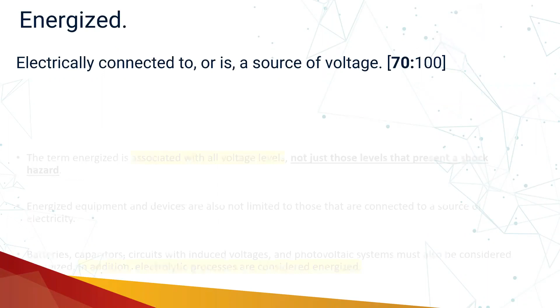We have seen that 50 volts and above represent a shock hazard. But if you are interacting with electrical equipment or systems below 50 volts, it will still be termed as energized, even though there is no potential for electric shock. Energized equipment and devices are not limited to those connected to a source of electricity; batteries, capacitor circuits with induced voltage, and photovoltaic systems must also be considered energized.